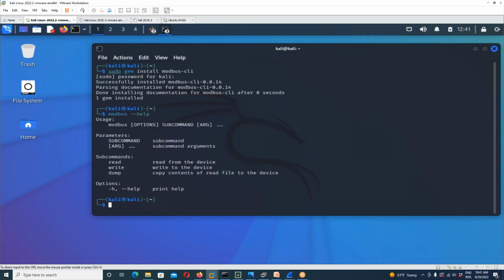What we want to do is try to read and write those coils on those facilities, similar to what we just saw in those Wireshark captures. So we're going to try to do exactly the same thing. One thing you need to know is the way Modbus and Schneider name their memory areas and the addresses of their PLCs. I'm going to throw this up on the screen for you in just a minute. Give me a sec.